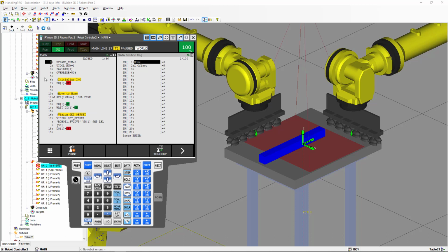Now we need to set up the handshake between the two robots. There are two ways we can do that. We can use a PLC to work as a middleman. The PLC is going to read the digital output from one robot and set a digital input on the other robot. The other way we can do that is to set a digital I/O communication between the two robots. I'm not going to explain how to do this I/O communication between the two robots on the real controller. It's not part of the scope of this video. Instead, I'm going to show you how to do that on ROBOGUIDE. We're going to select SAL.